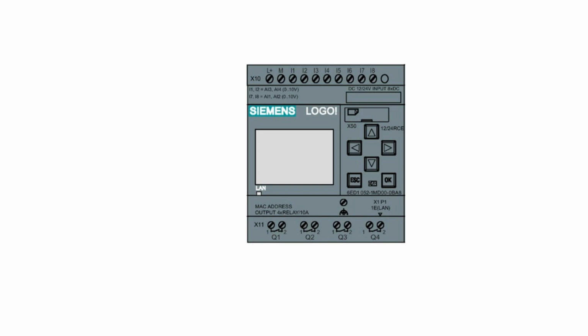The Siemens LOGO PLC is a relay-based PLC, so on my output side on the PLC we have 4 normally open contact outputs. Here we can decide the voltage we want to connect to them once they are triggered. Since I will connect a 24 voltage DC lamp, I will connect 24 voltage DC to the left terminal of the relay output.